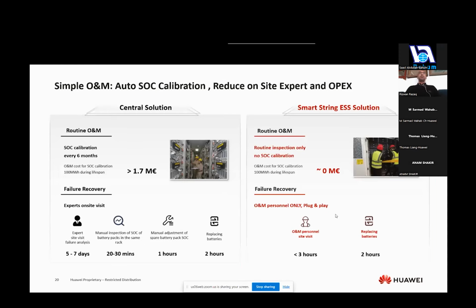So simple O&M and auto state of charge calibration, reducing the site expert and OPEX costs. As everything is monitored through the operating system, we can do all of the state of charge calibration remotely and not requiring a specialist engineer either from our partner or from our service engineers directly on site. So with an O&M issue occurring within 3 hours, we would be able to diagnose that issue, and if required within 2 hours, we'll be able to do a replacement battery on a pack level rather than as an overall solution.